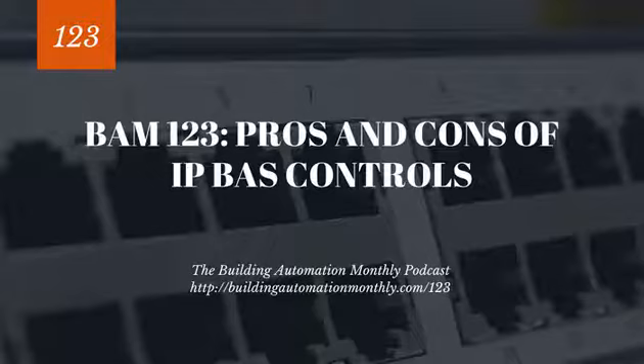So usually star pattern is utilized for major controllers. It's utilized for air handler controllers and maybe central plant controllers, but it's not typically utilized for terminal unit controllers, as those are high density. For a chiller, you may have 3 or 4 chillers in a large building. And in a large building, you may have 20, 30 air handlers, but you may have 200, 300 terminal units. So you can see the controller density is a factor of 10, right? 2 to 3 chillers, 20 to 30 air handlers, 200 to 300 terminal units. Those are just rules of thumb, but they tend to play out that kind of factor of 10 increase to your count of your actual controllers.